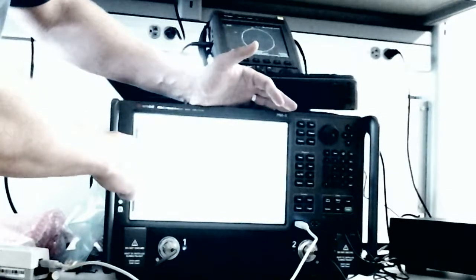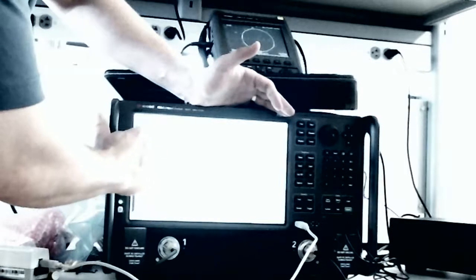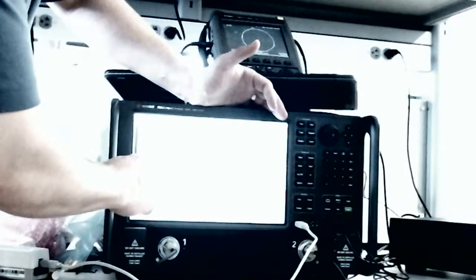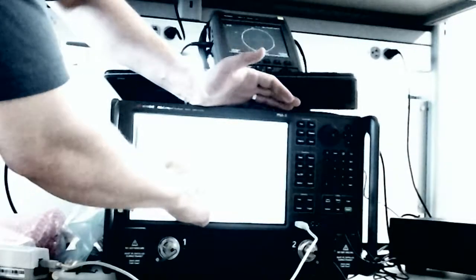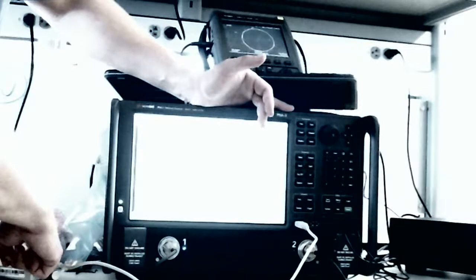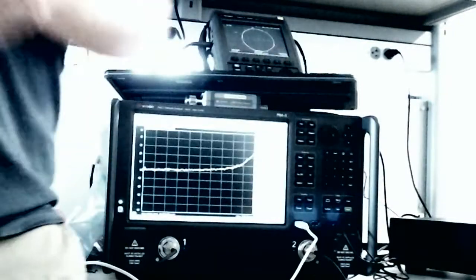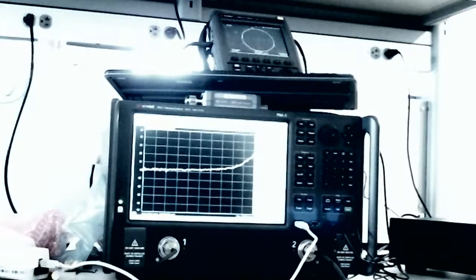And the last thing is the noise figure, right? So part of the noise figure setup, you can see, under impedance states, you see how it says noise tuner? There's none selected here because it only has this ECal connected. So let me close this and let me connect the other ECal, and we'll talk a little bit about what happens there.